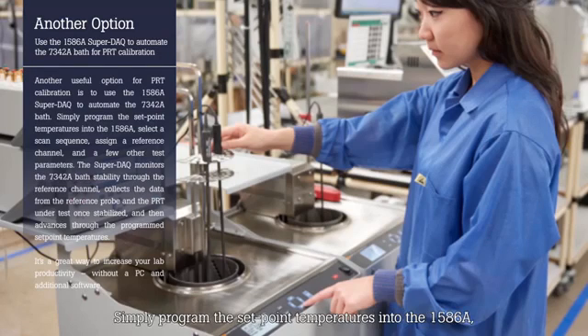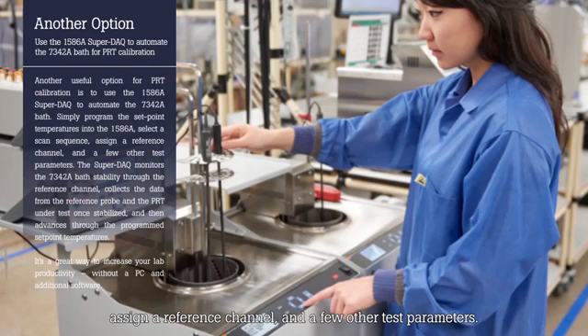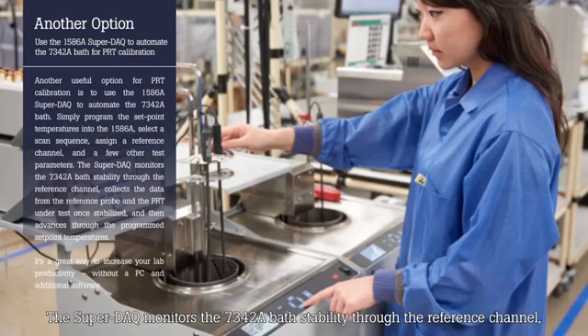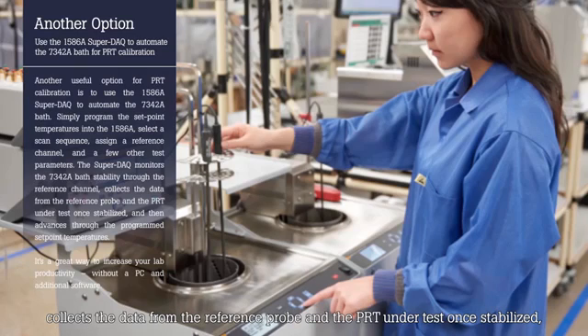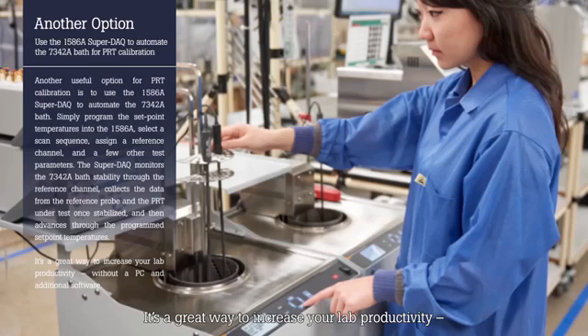Another useful option for PRT calibration is to use the 1586A Super-DAQ to automate the 7342 bath. Simply program the set point temperatures into the 1586, select a scan sequence, assign a reference channel, and a few other test parameters. The Super-DAQ monitors the 7342A bath stability through the reference channel, collects the data from the reference probe and the PRT under test once stabilized, and then advances through the programmed set point temperatures. It's a great way to increase your lab productivity without a PC and additional software.